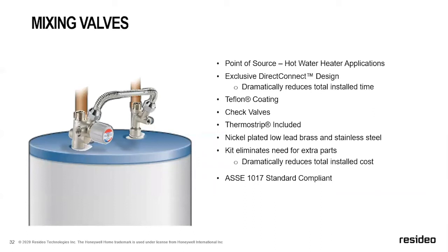It is for point of source hot water heater applications. There's an 8-inch spread shown there, but if you have a larger tank and you need to go to 11-inch, we do offer that too. It's Teflon coated, which is really nice for any buildup that you might have over time. This is Teflon, so it's coated inside. It will extend the life of this device. Nickel plated and low lead, brass and stainless steel, and the kit eliminates any need for extra parts. So brand new heater installation, you can really get this installed within a matter of minutes and add a lot of value to your customers.